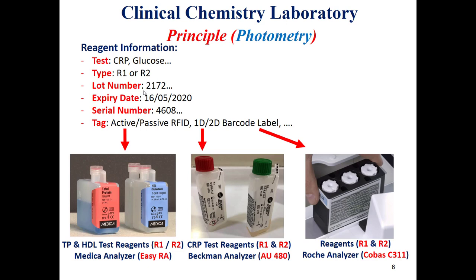The lot number is very important. This lot number will be changed every four to six months, depending on the production of this reagent by the manufacturer or supplier. We also need to know the expiry date for this reagent. There is a lifetime for this reagent, and usually to keep it within this lifetime, we should keep it at 2 to 8 degrees to avoid evaporation. In addition, we should know the serial number of this reagent.